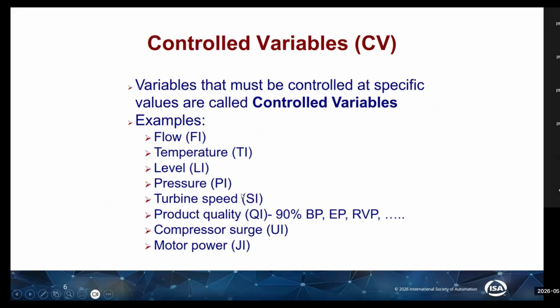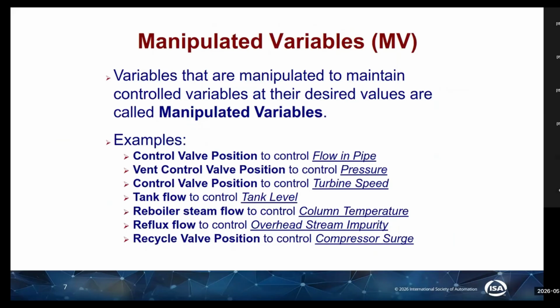So this is our CV. It can be flow, temperature, level, pressure, whatever. And then we have something called MV, which I already explained. Typically, it's the valve, or fan speed to cool down, or whatever. So this is also the manipulated variable.